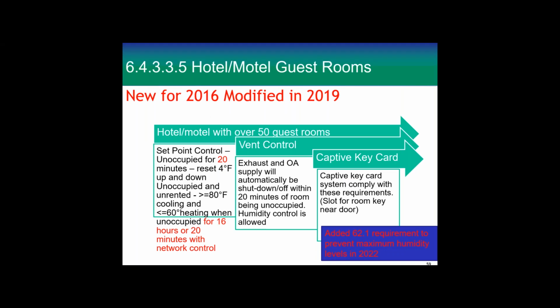New for 2016, modified in 2019. We did quite a bit of work on hotel guest rooms, and we changed it again, modified in 2019. Set point controls: unoccupied for 20 minutes, reset 4 degrees up and down, unoccupied and unrented.